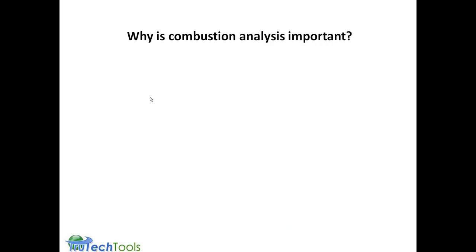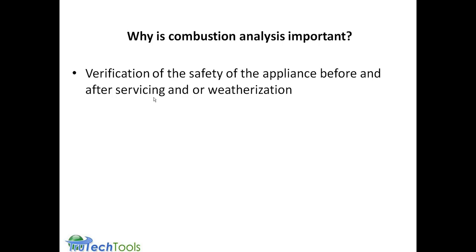So just to start off with, we want to understand, why are we even using a combustion analyzer? Why is combustion analysis important? We use it for the verification of safety of the appliance, especially before or after service and or weatherization, any kind of air tightening work. If you take the combustion analysis class, you find out how important the presence of the correct amount of air is in terms of combustion air, dilution air, ventilation air, leakage air. All these things affect the envelope of the house and the way the combustion appliances run. So when you change or alter the air that's available through weatherization, then you could change or alter the combustion process and cause a safety issue.